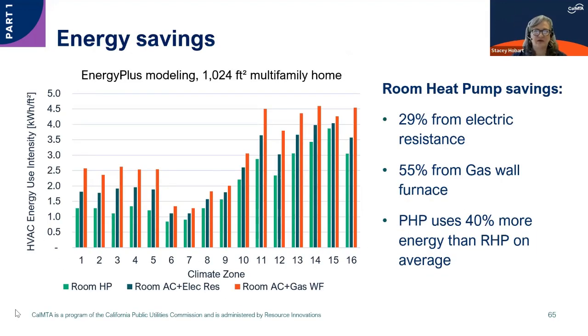So he's looking at whether the efficiency of cooling is the same for the base case. That's a good thing to point out. In this case, we were assuming that there is even efficiency on cooling between the heat pump and the window AC. So all the savings here are on the heating side. If you look at the CEER level of these saddlebag units, they're around 16, which is also the federal minimum for window ACs coming in 2026, when we're actually active in this MTI. So we think that the benefit's going to come on the heating side in terms of bill savings, or any bill impacts, but also all the energy usage.